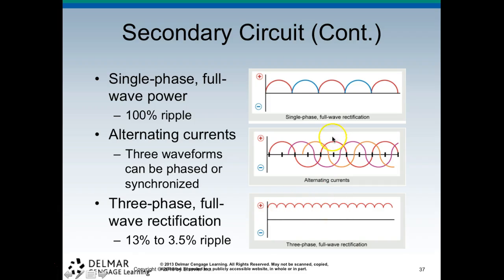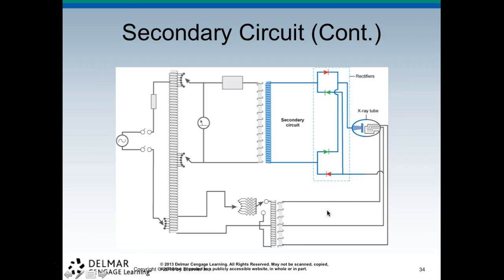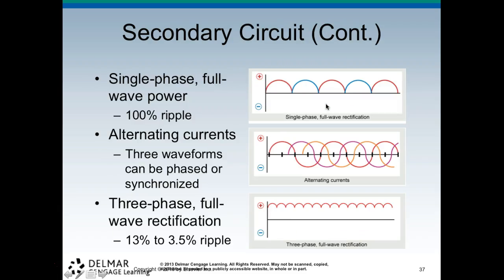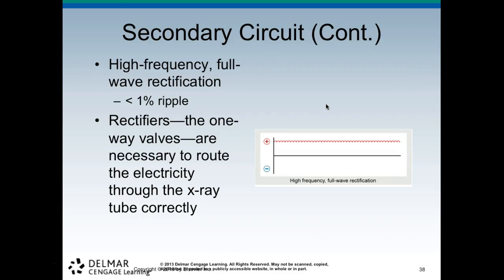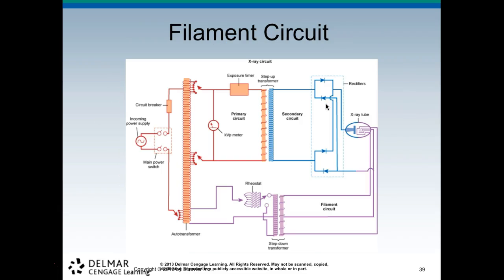So this is alternating, and now we're at three-phase full rectification. That's in this portion here. We've got our rectifiers here. All right, high frequency is full-wave rectification with 1% ripple. Rectifiers are one-way valves and are necessary to route electricity through the X-ray tube correctly.